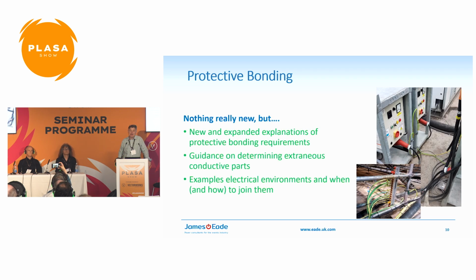Protective bonding, nothing really new. There's no changes to this from a standards perspective, but what I have done is provided more clarity on what is an extraneous conductive part, what needs bonding and what doesn't. Again, lots of things from cable bridges to Harris fencing, you see green and yellow wires strapped to it, which shouldn't have them at all. And there's a particular need to make sure that you don't actually introduce faults where faults don't need to be, and people have been injured by being in contact with random bits of metalwork that someone's earthed, which it shouldn't have been, or bonded, I should say.